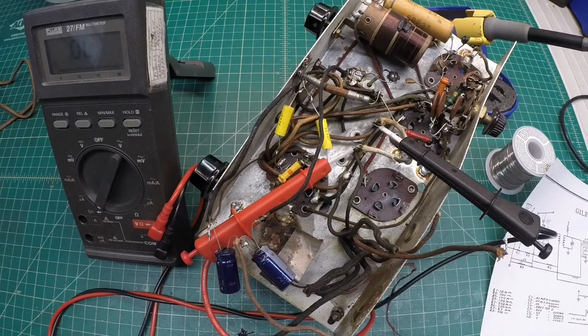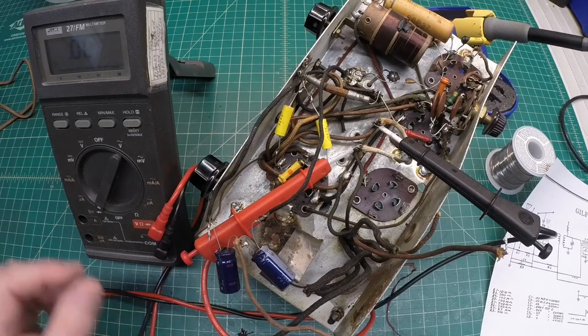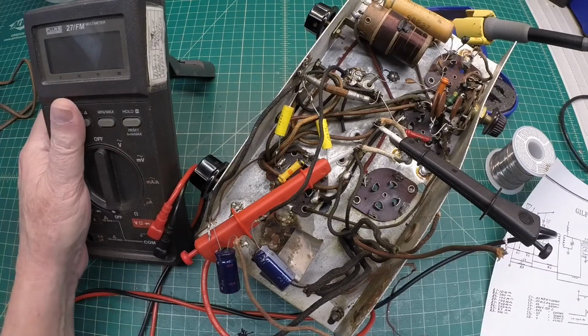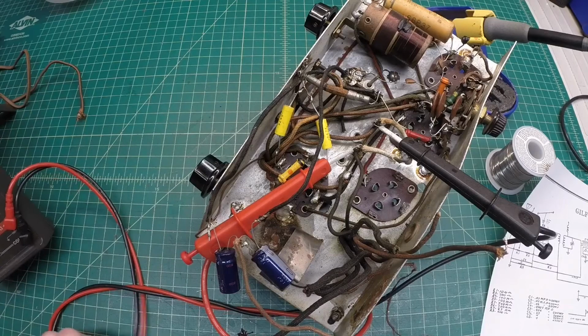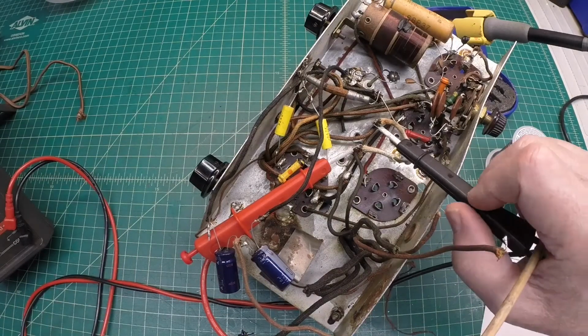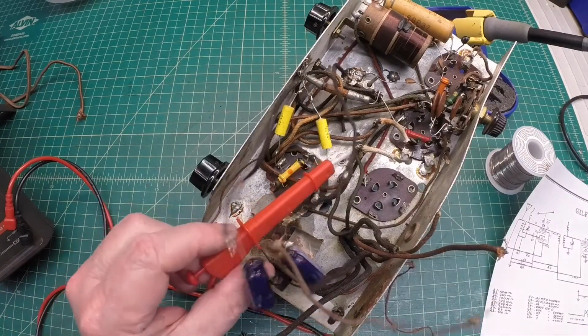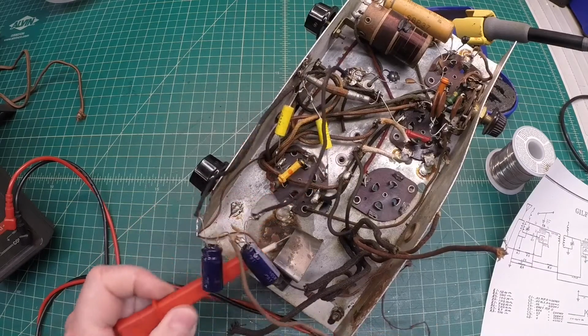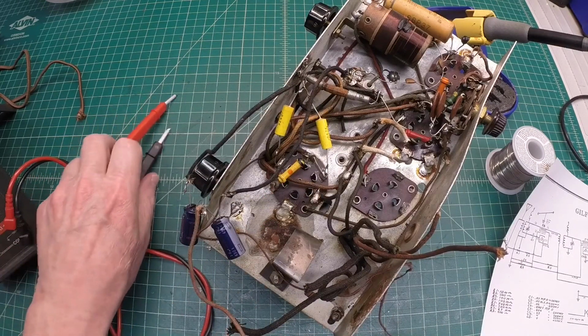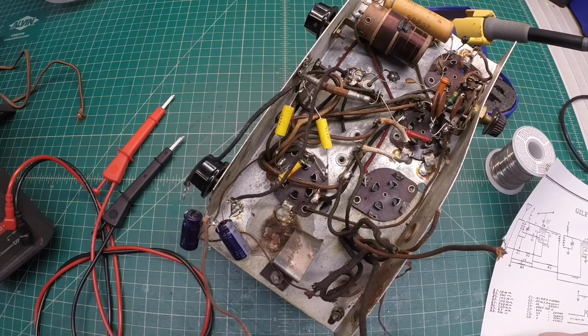Here in just a bit we'll go ahead and read the primary DC resistance of the transformer as well. You'll typically read anywhere from 8 to maybe as high as 20 ohms or so, but I usually see 10 to 15 ohms of DC resistance on the primary side.